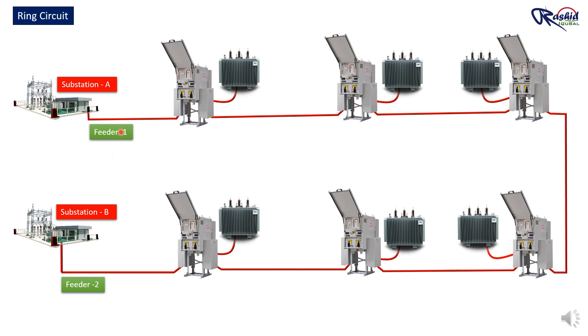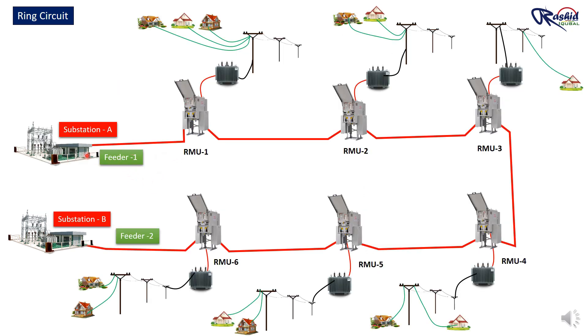Through this layout, I am trying to explain how the system works. In this ring main distribution network, we have two feeders — Feeder 1 and Feeder 2 — supplying power to 6 transformers, each connected through their respective RMU to the feeders. Normally, power flows from Feeder 1 through each RMU, which then supplies electricity to the connected transformers. Each transformer steps down the voltage to a level suitable for the load, like homes, offices, and other buildings.